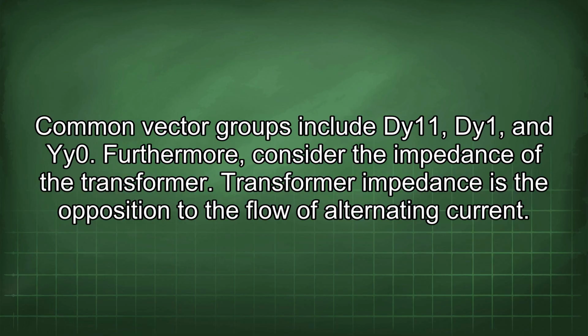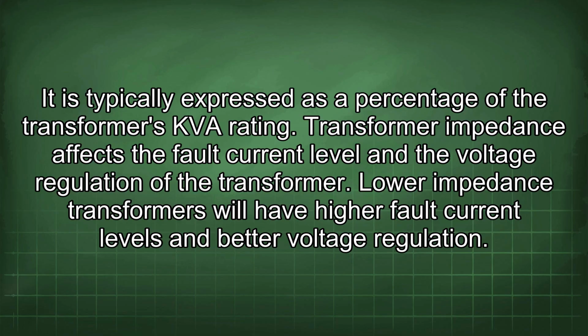Furthermore, consider the impedance of the transformer. Transformer impedance is the opposition to the flow of alternating current. It is typically expressed as a percentage of the transformer's kVA rating. Transformer impedance affects the fault current level and the voltage regulation of the transformer. Lower impedance transformers will have higher fault current levels and better voltage regulation.